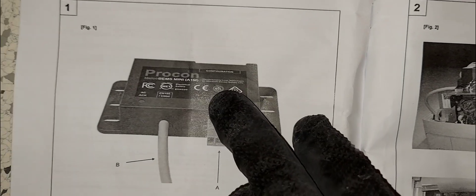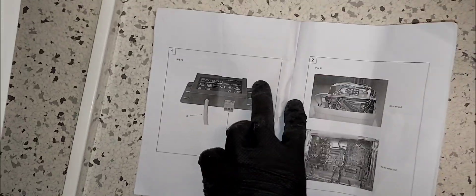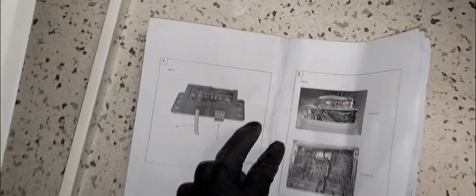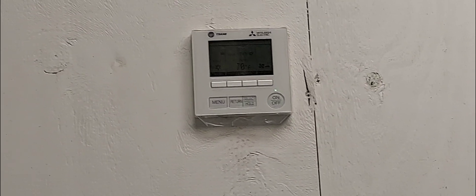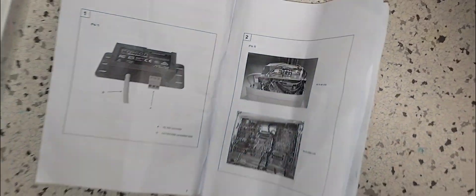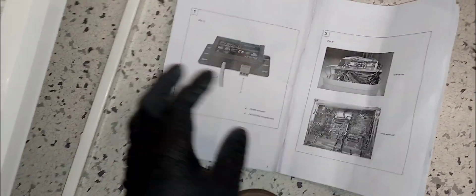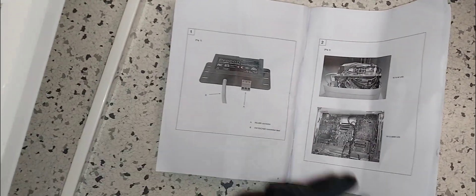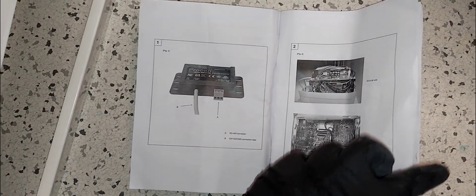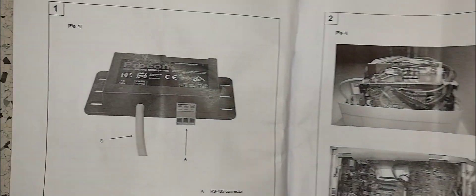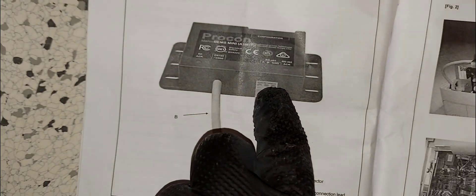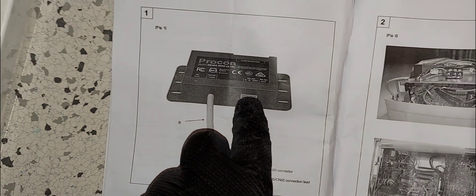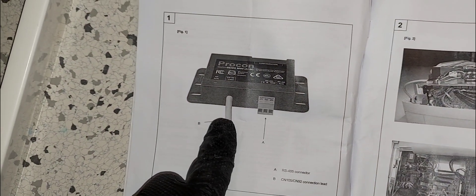What this device does - a regular mini split here is your thermostat as you all know. It takes a regular mini split and enables it to be controlled by your BMS or building management system. This right here uses RS485 and this you plug into your main board.